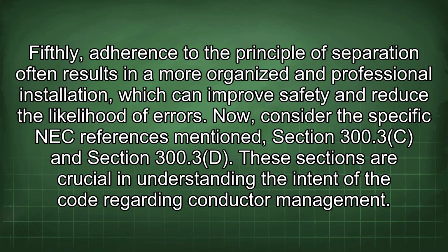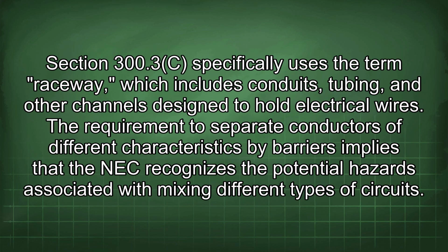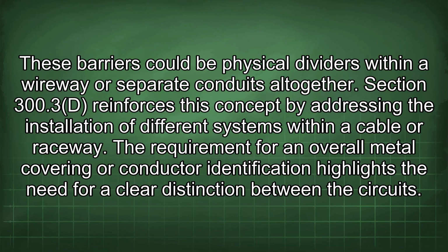Now, consider the specific NEC references mentioned, Section 300.3c and Section 300.3d. These sections are crucial in understanding the intent of the code regarding conductor management. Section 300.3c specifically uses the term raceway, which includes conduits, tubing, and other channels designed to hold electrical wires. The requirement to separate conductors of different characteristics by barriers implies that the NEC recognizes the potential hazards associated with mixing different types of circuits. These barriers could be physical dividers within a wireway or separate conduits altogether.